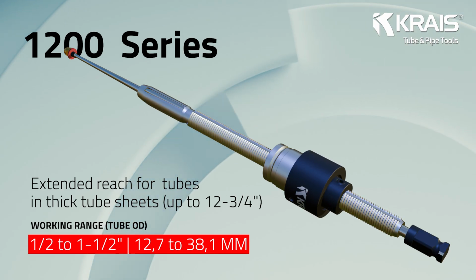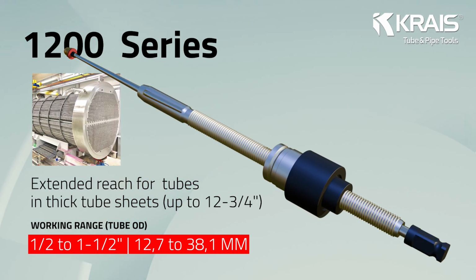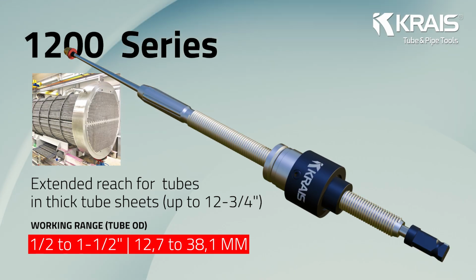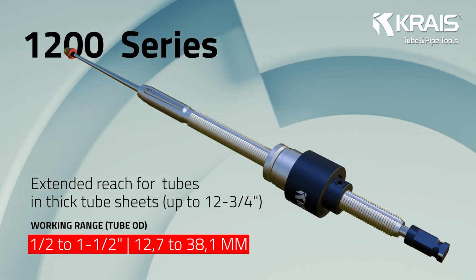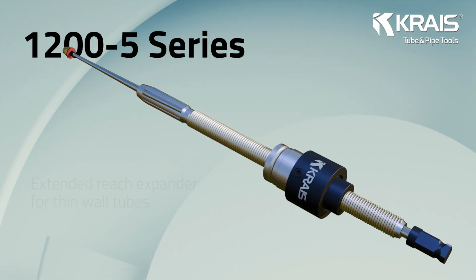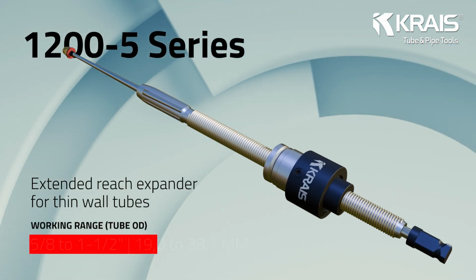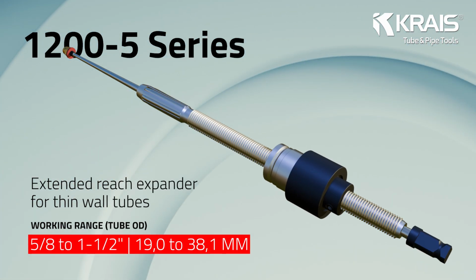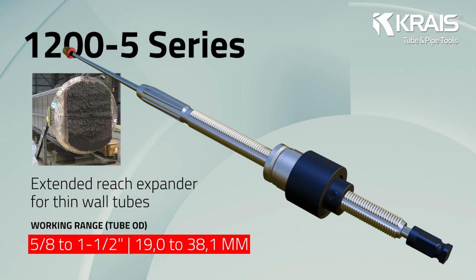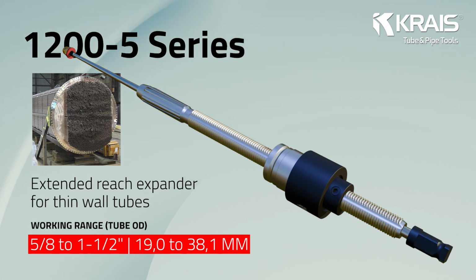not provide adequate reach. In practice, reach variants are selected to match tube sheet thickness, and the cage length and tooling geometry directly define the effective roll zone. KRAIS 1200-5 is the 5 rolls series: these expanders combine extended reach with a 5-roll forming profile.